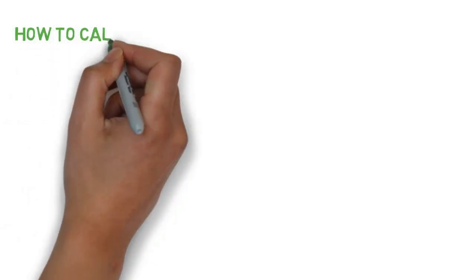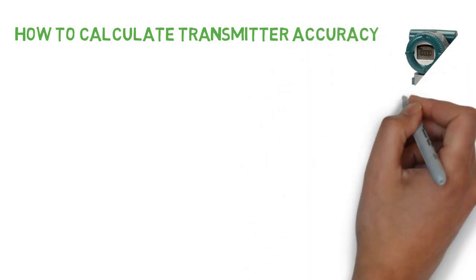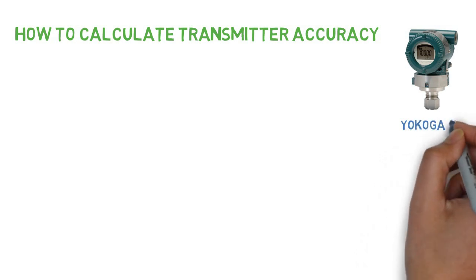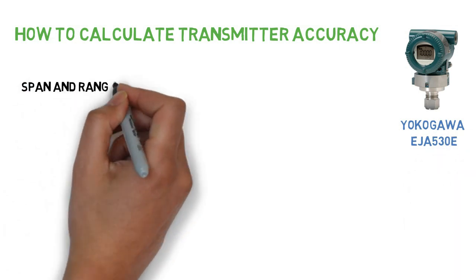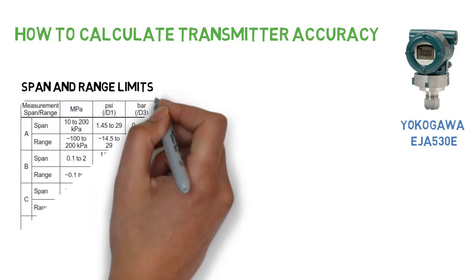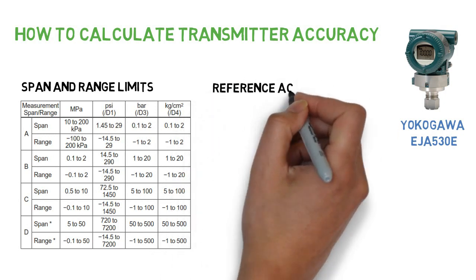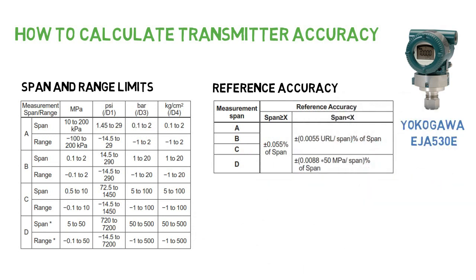How to calculate transmitter accuracy? Consider Yokogawa pressure transmitter of EJA530E model. Span and range limits of this model is given in below table. Reference accuracy of this model is given in below table. These tables can be found in the product catalog of this model.